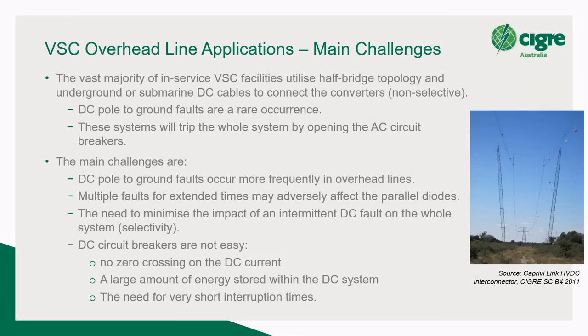DC circuit breakers are not so easy. Most of us will understand that an AC circuit breaker opens up on the zero crossing. There's no zero crossing on the DC current. And you've got all this energy stored in the DC system. And sometimes your DC system is connected to a renewable energy source at the other end. So, given the need for short interruption times, you want to be able to stop that current as quick as you can so that you don't impact your parallel diodes.